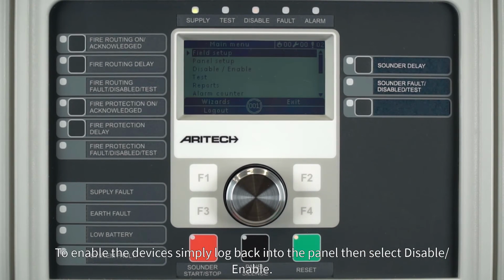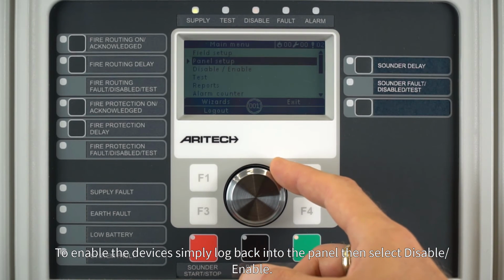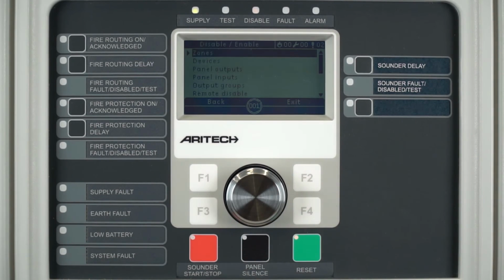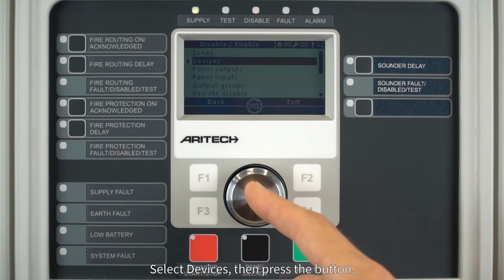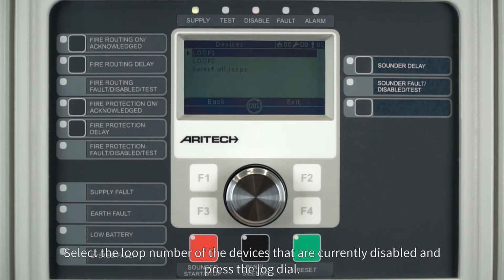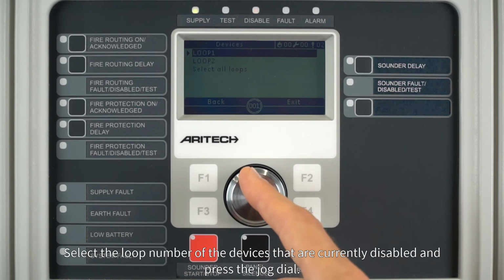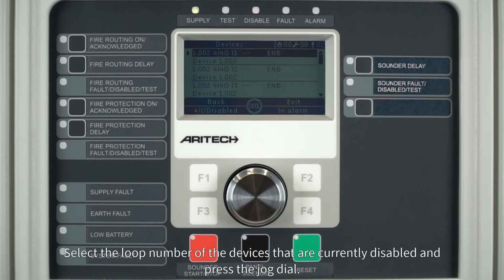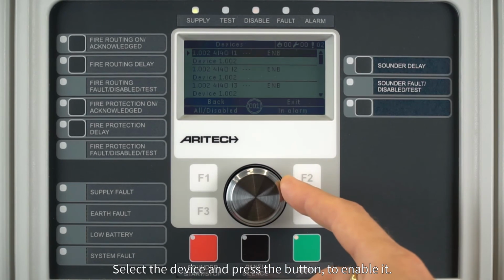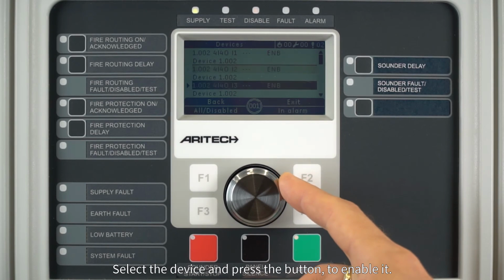To enable the devices, simply log back into the panel, then select Disable Enable. Select devices, then press the button. Select the loop number of the devices that are currently disabled and press the jog dial. Then select the device and press the button to enable it.